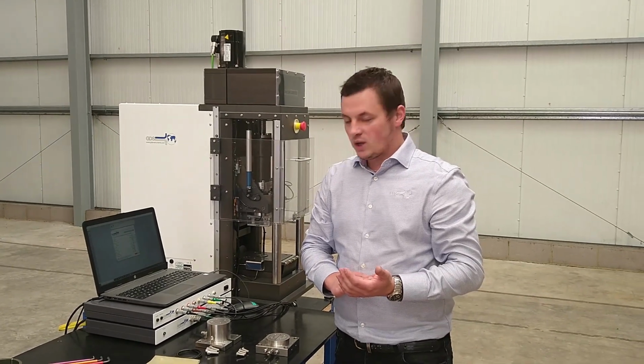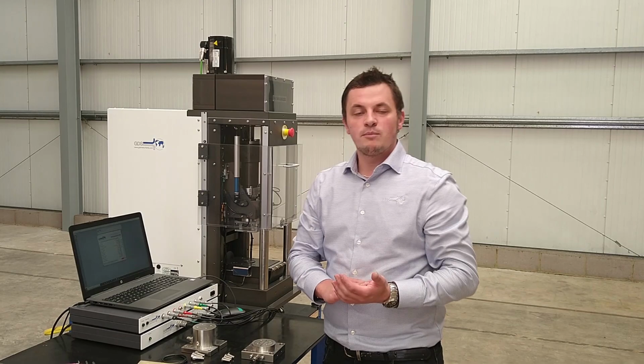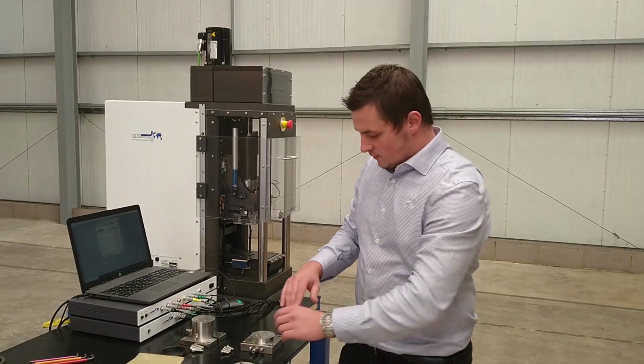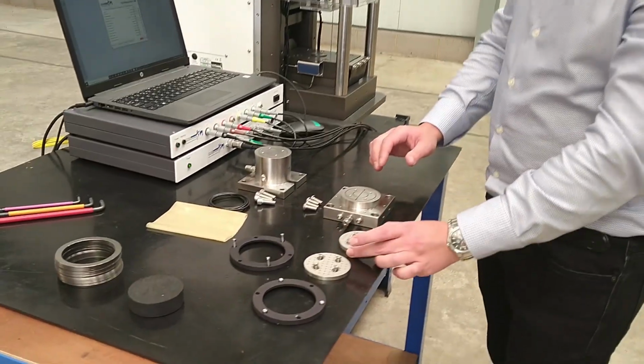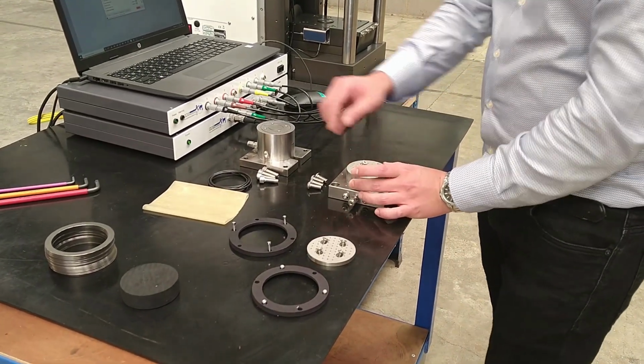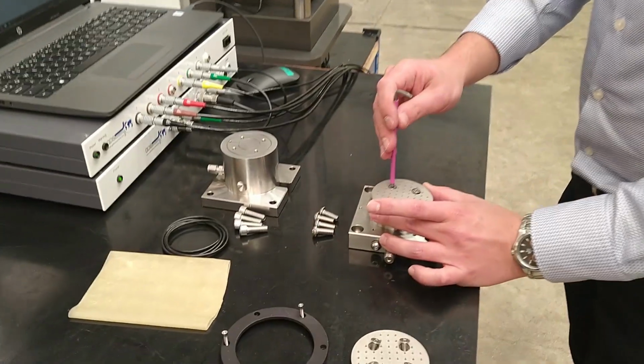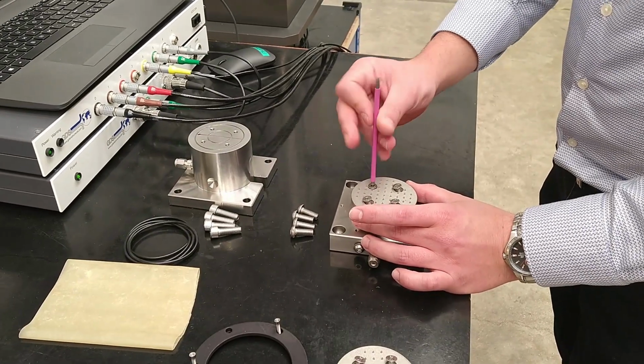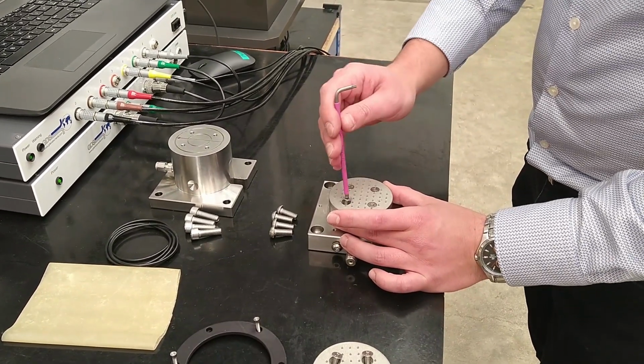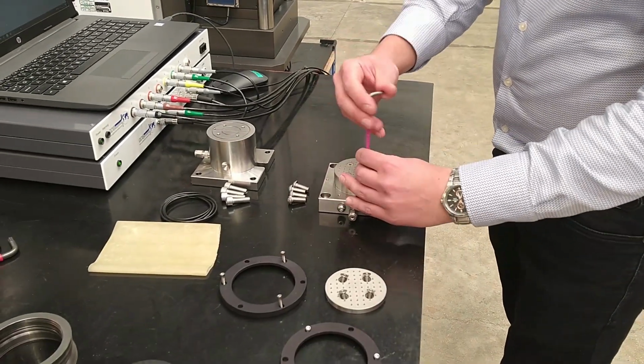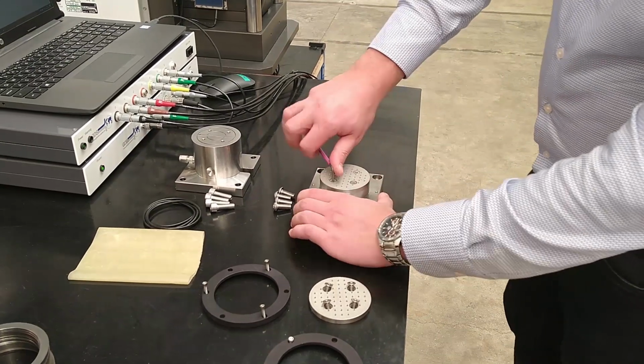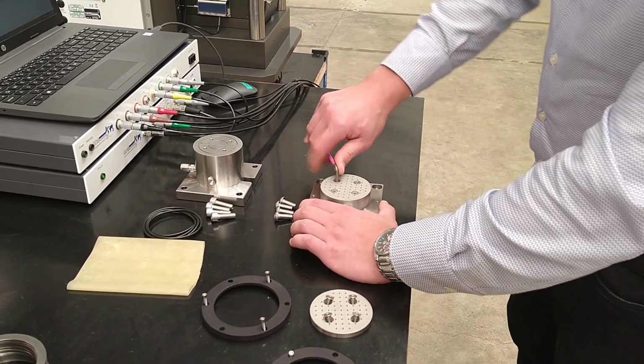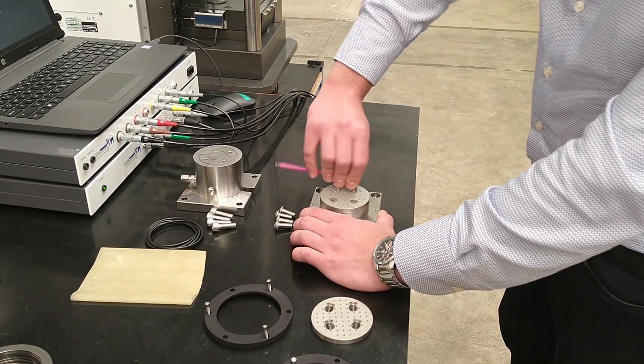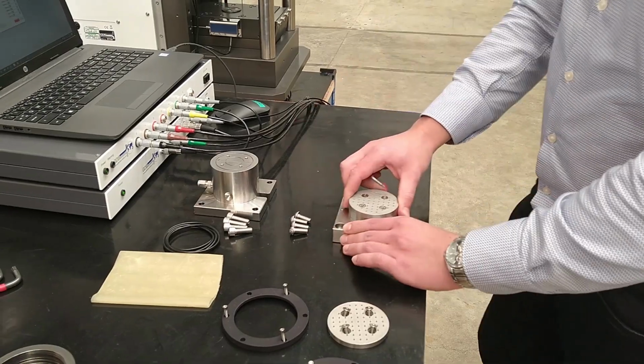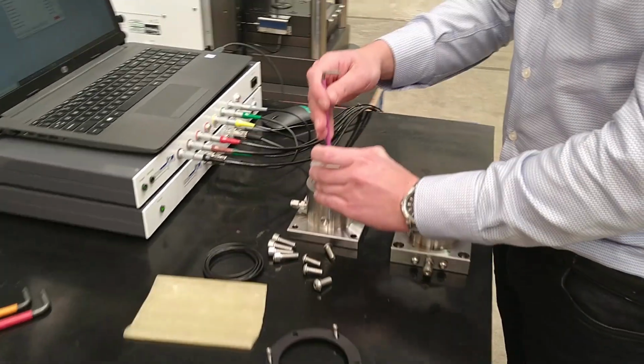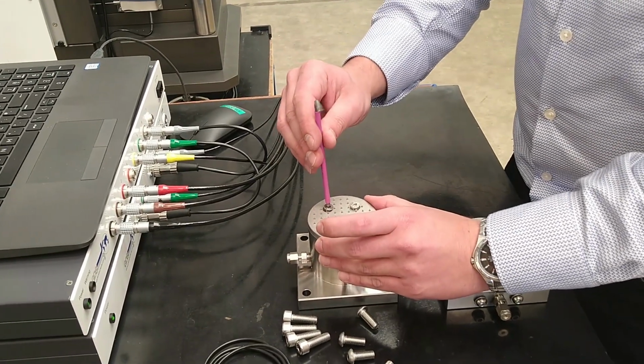Okay, so now we'll have a quick look at the initial setup of the sample set assembly, including the pedestal and the top cap. So we'll start with bolting the porous discs onto the pedestal. Please make sure that the bolts holding the discs are very tight, because they'll have to carry the shear force on the sample. So you can do the same for the top cap.